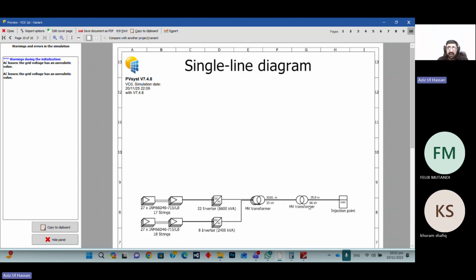But in most cases, the client will give you the overhead connection point in your PV area, so you just connect your system to that. It is possible that we may have to provide a 1 kilometer, 2 kilometer or 5 kilometer transmission line. But in most cases, the client will give you the transmission injection point in your PV area, so you just connect your cables at the injection point the client has given you.